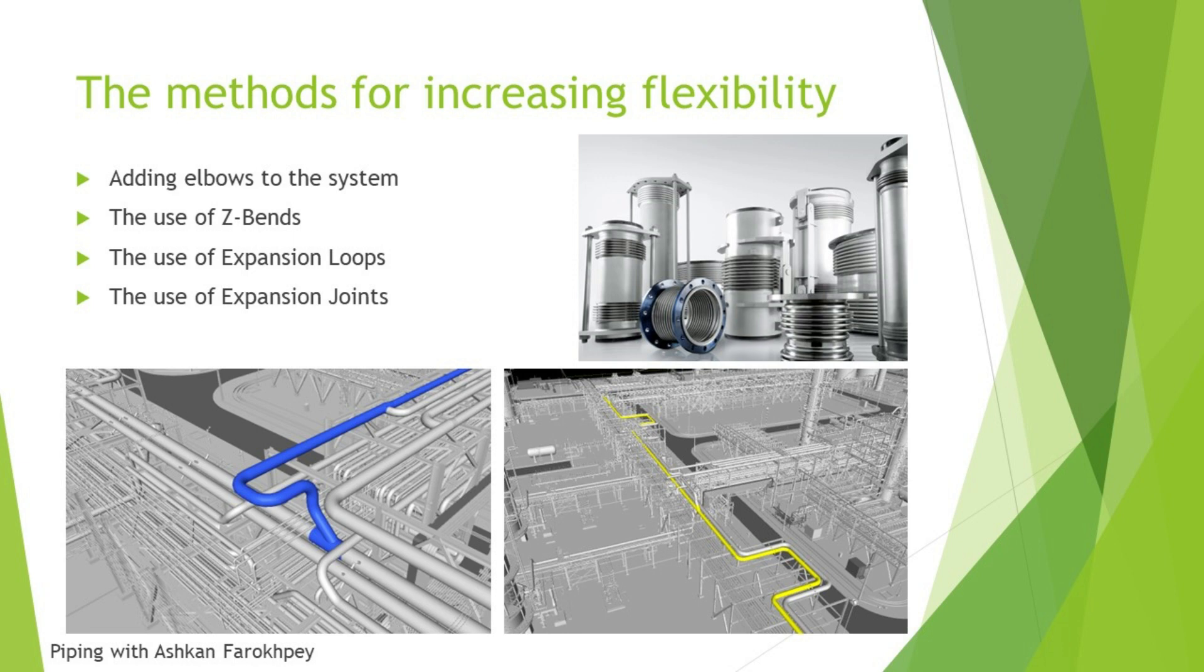The second method is using a Z-bend. The third method that you can see in the bottom pictures is using expansion loops, and we will use these two methods, method two and three, in CAESAR II. It is commonly used in piping systems to control the thermal expansion. And the final method, which is used in compact piping systems, is using expansion joints. The last method is much more complicated and I will upload a new video for using expansion joints, which is mostly used around the pumps in oil and gas industry.